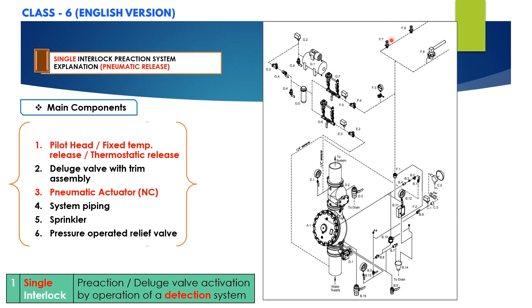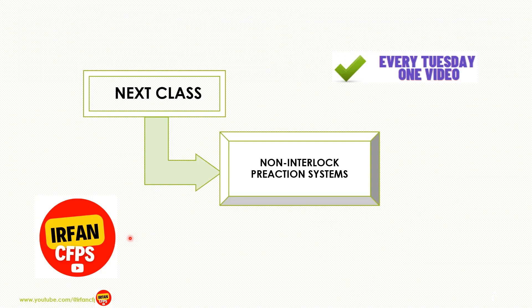Pilot head and fixed temperature releases are closed type sprinklers; the thermostatic release opens to allow pressure in the release system to escape. As shown in the schematic, the air compressor piping is connected to the system piping for pressurizing, and this network is also connected to the pneumatic detection system. In fire condition, operation of the pneumatic release system opens the deluge valve to fill the system with water. If any sprinklers have opened, water will flow from the system; if not, water remains in the sprinkler system piping until the sprinklers operate. A sprinkler head must open before water flows from the system. In the next class, we shall learn about non-interlock pre-action systems.